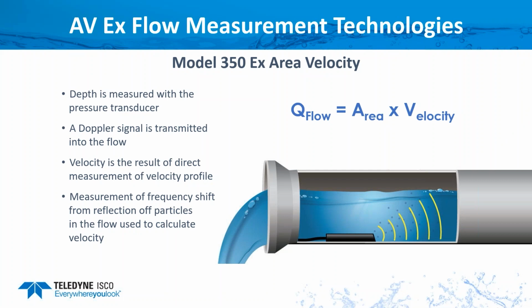Now we'll just take a quick look at that. So here's an area velocity sensor mounted in a pipe. To read flow, we just need to know the area and velocity to calculate flow. So we have a pressure transducer that's going to read the water depth to calculate the wetted cross-sectional area in your pipe. It's going to transmit the Doppler signal, and it's going to read the frequency shift to tell us the direction of the flow and the velocity. So we'll read both direction and speed. And with that, now we know the level for the area, the velocity, we can calculate the flow.